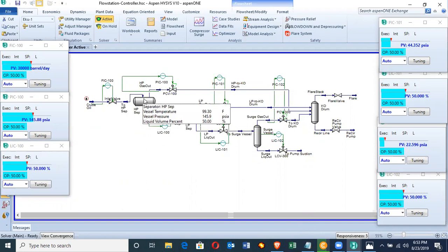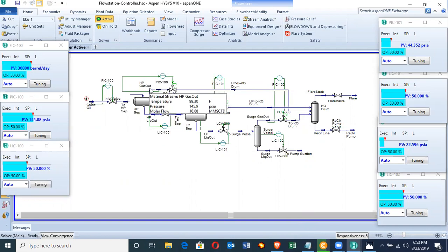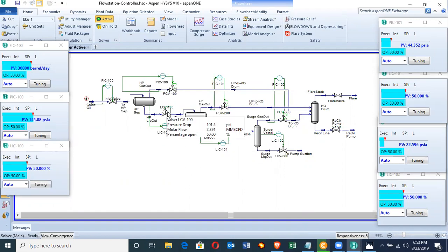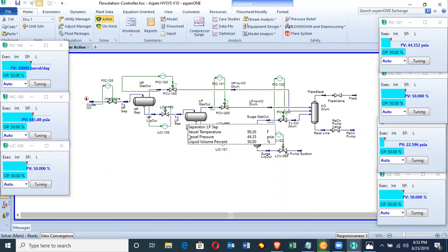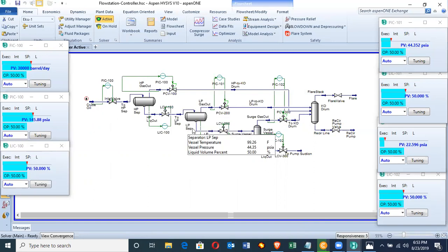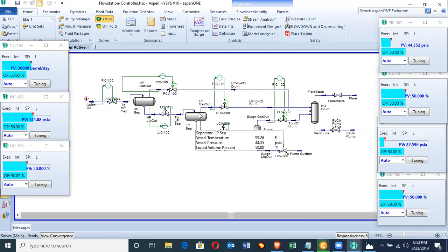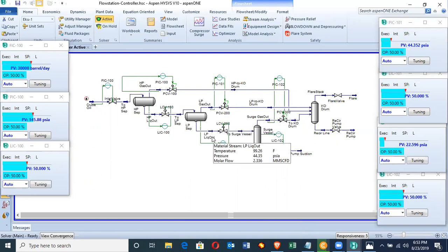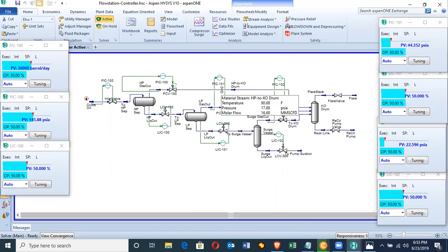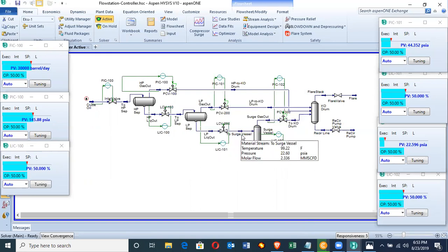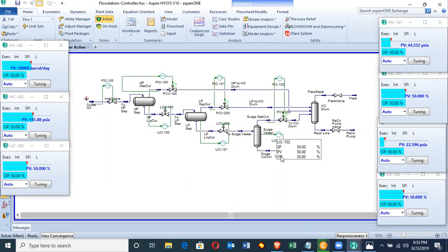In the HP separator, gas is flashed off. Most of the gas has been flashed off here, especially methane. While the liquid portion flows through the LCV, the level control valve, and gets into the low pressure separator. Within the LP separator, further separation of gas and liquid takes place. Gas is being flashed off and liquid goes through the level control valve to the surge vessel. From the surge vessel it gets to the export pump.